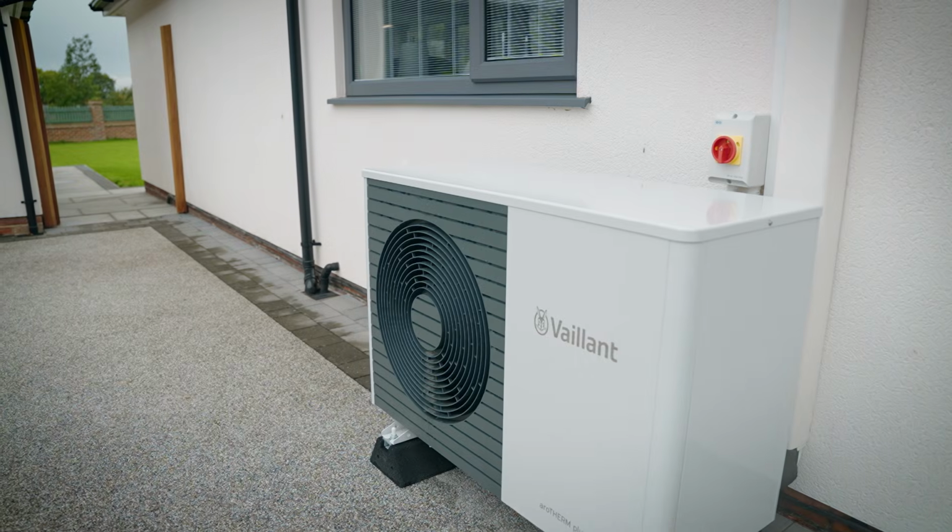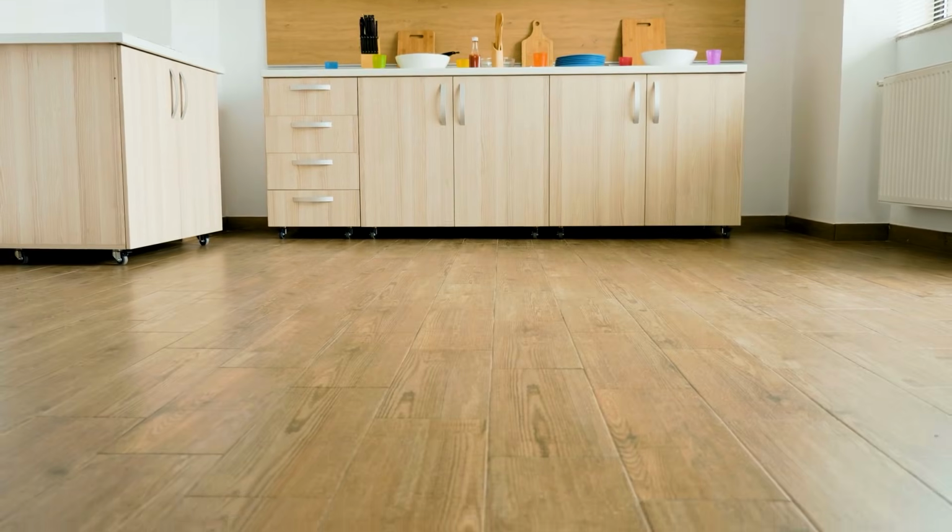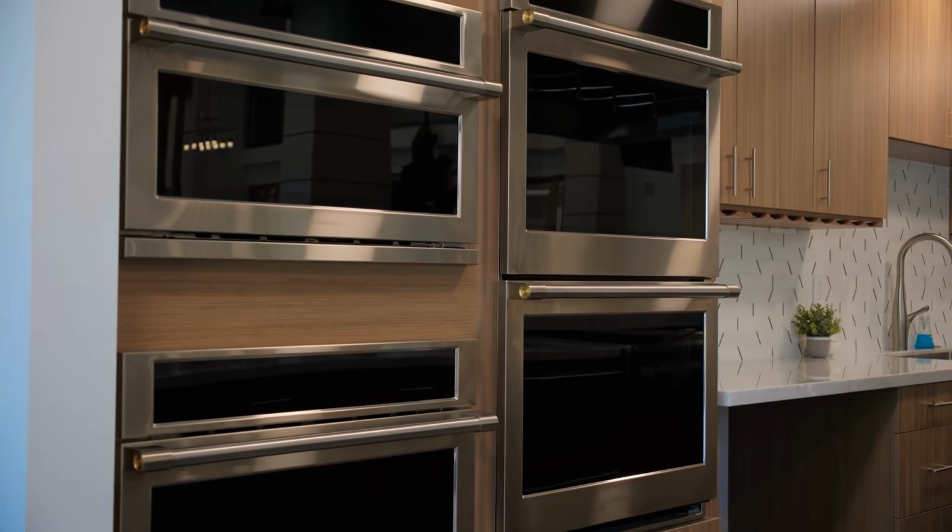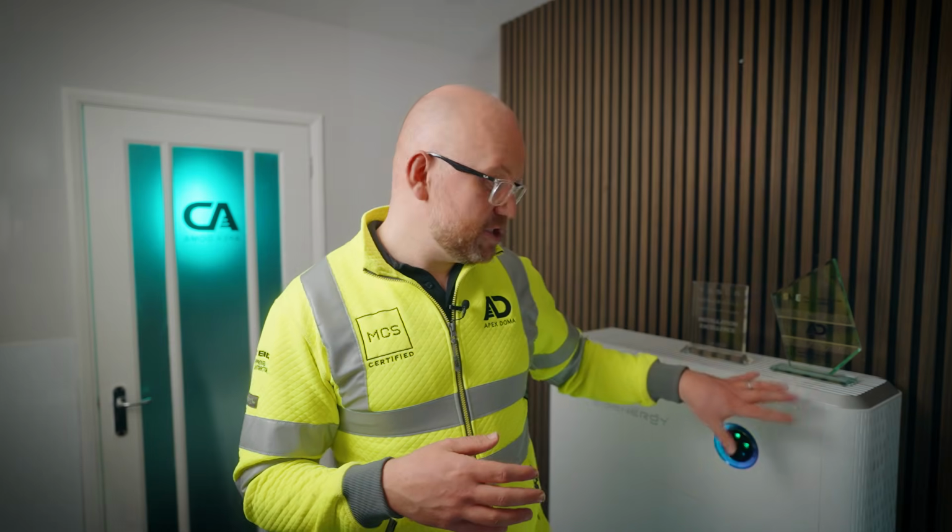Then, if you're a much higher demand household user, for example, some of the properties that we've seen with heat pumps, hot tubs, underfloor heating, bigger cookers, you might have 2 ovens, for example, then in that scenario, we're going to be looking at the bigger size again. Now, this isn't an indefinite size where we can just keep going and going. There are limits to how fast we can pull power through and meet the demand to your home. Normally that sits about 12 kilowatts as a maximum on a single phase supply. Like the Sigenergy SigenStore, the inverter behind me, they make a 12 kilowatt version.